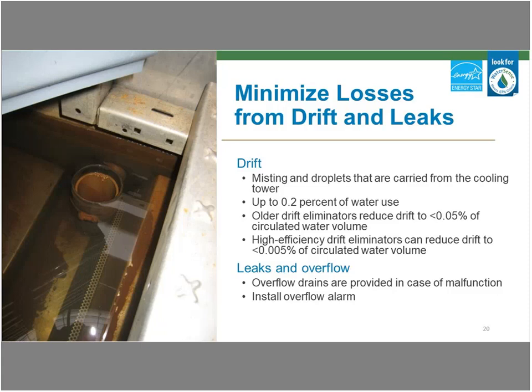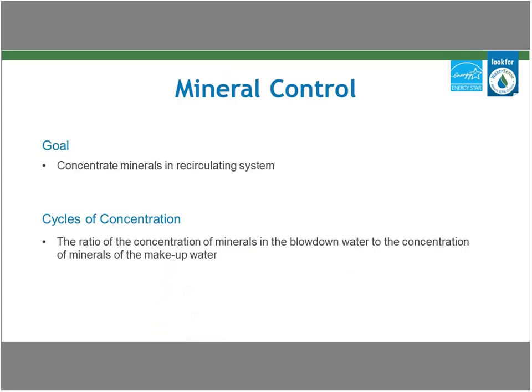Water was constantly flowing, overfilling the basin, and going down the drain. This is a good thing to try to check on daily rounds. Some newer systems also have BAS alarms that you can connect to your building automation system and can alert the operator to an overflow event. So if you get one of these alarms, or if you hear water flowing down the drain when you're near your tower, this is definitely something you should remediate, as water use from these overflow events can be significant.